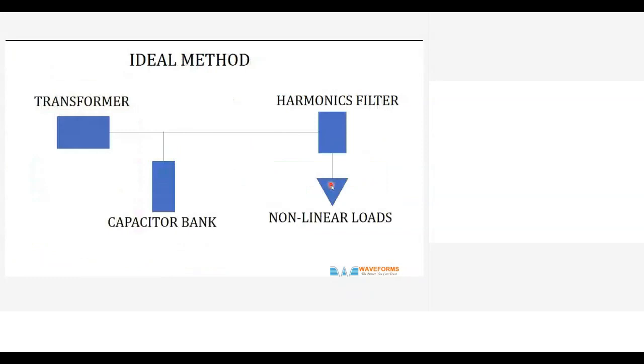So the ideal method, from my experience and expertise, is filtering these harmonics closer to the non-linear loads. Suppose you have, say, a data center in your plant. Isolate that and put filters there to reduce the harmonics, and then it becomes very simple. Rather than using an active filter at the panel, allowing the harmonic currents to flow inside the plant and then filtering them closer to the transformer is not an ideal method. The ideal thing is at the non-linear load.